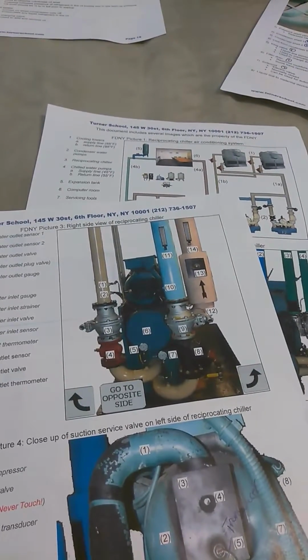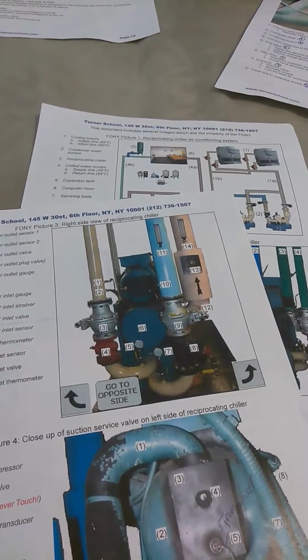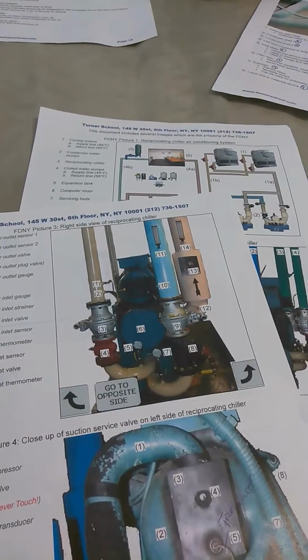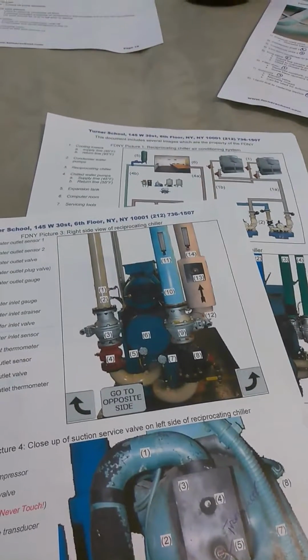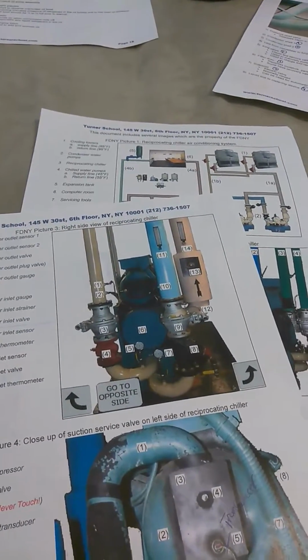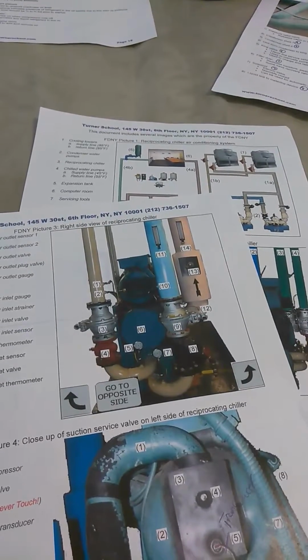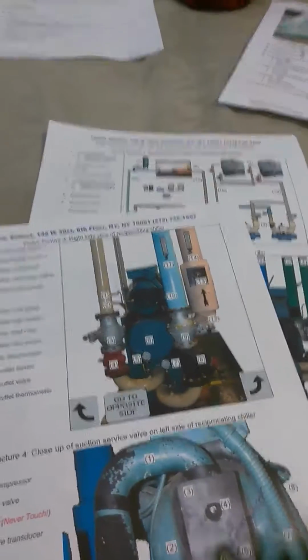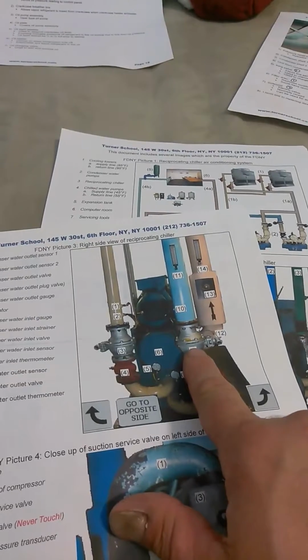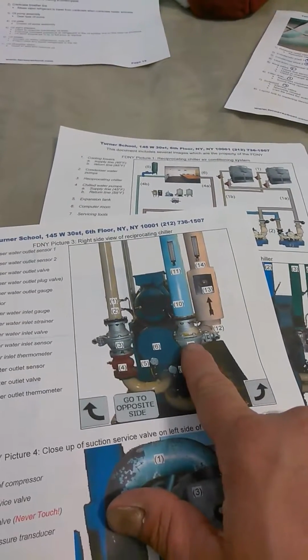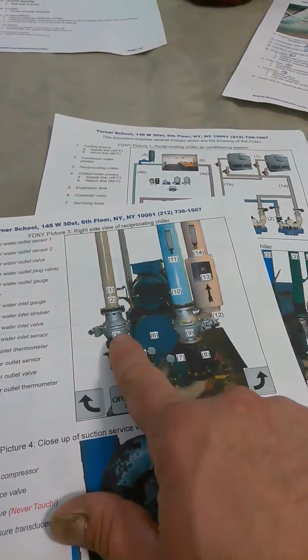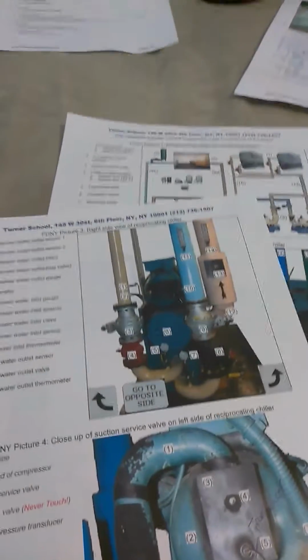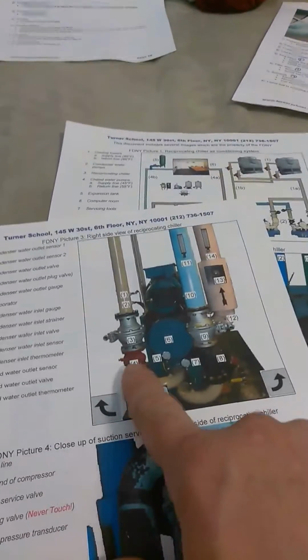Open the chilled water inlet. Open the chilled water outlet. Open the condenser water inlet. Open the condenser water outlet valve. Then the condenser water plug valve, the big one over here.